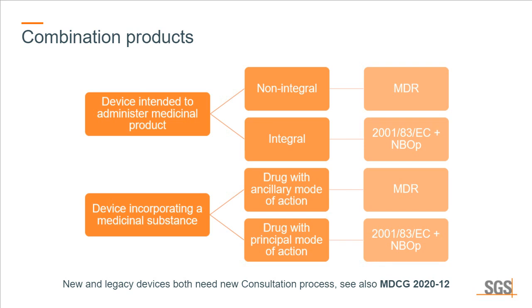And then in the first case, you have to look at whether it's an integral part or not integral part. And the second one, is it a drug with an ancillary mode of action or a drug with a principal mode of action? Depending on these selections, your device might be regulated under the MDR or under the pharmaceutical regulations, which may require a notified body opinion. So in some cases, for example, if you have a device that is primarily used to deliver drugs, like a pre-filled syringe, then maybe the overall thing will be considered a drug and will be regulated as a drug.